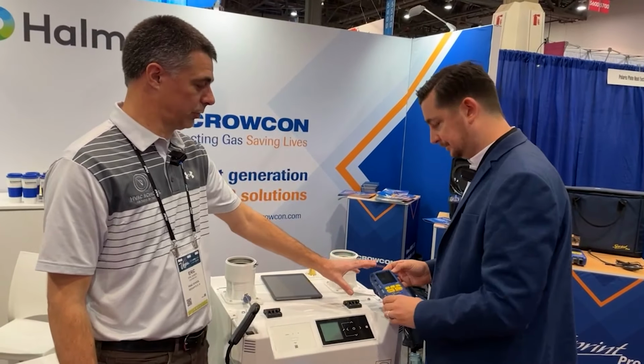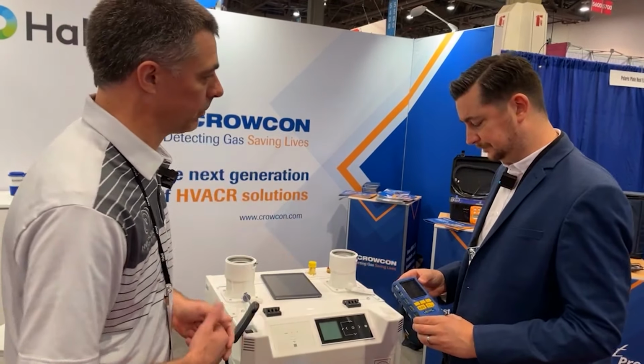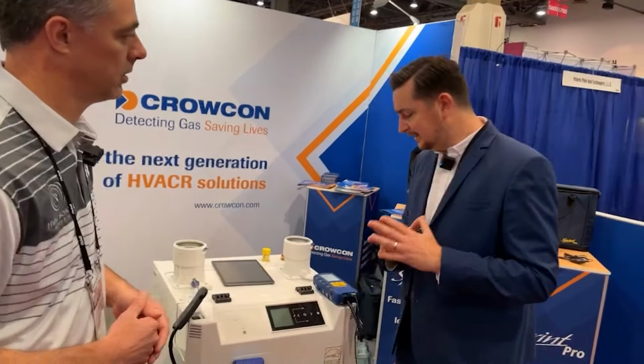Now, how many gases will that handle for typical flue gas detection? Okay, so in flue gas detection, as standard, we do 6 different models. They all have oxygen in there. They all have CO in there, and they all calculate CO2. So you're going to get CO, CO2, and oxygen, no matter what model you choose. We do a few higher end models. They have NO sensors in that allow you to do NO, NO2, and NOx from the one sensor. Yep, which are very important in some models and some appliances.